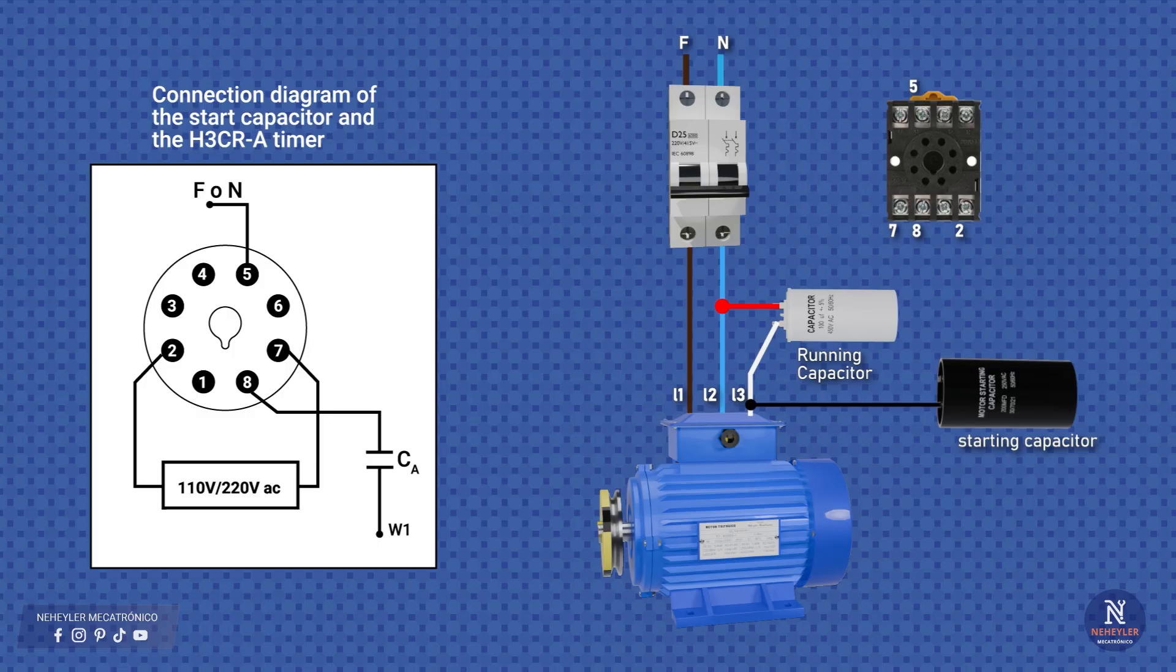Now let's see how to make the complete connection. On the left we have the wiring diagram, where it is clearly shown how the start capacitor goes through the H3CR-A8 timer. On the right we see the representation with the real elements, the circuit breaker, the motor, the capacitors, and the timer base. This timer has 8 connection terminals, and for our circuit they must be wired as follows. Terminals 2 and 7 are the timer supply, here we connect phase and neutral that come from the circuit breaker. Terminal 8 is the common contact, from which we take the connection to the start capacitor. Terminal 5 is the normally closed contact, which completes the circuit to neutral or to the other line, depending on the required rotation direction. Finally we place the timer on its base to leave it ready.